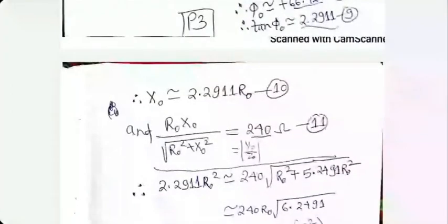What I'm trying to do here is experimentally determine the equivalent circuit parameters of the core. No load test is the name for this kind of situation, when you connect nothing to the secondary and you measure the input current. This is an experimental method of measuring core parameters R0 and X0. That's what they are doing in this problem.